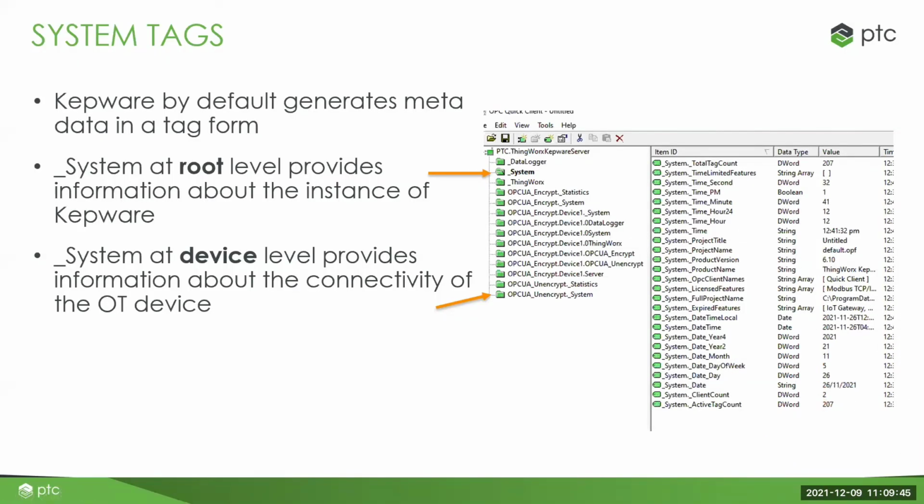For example, in certain cases maybe an HMI has some bug in it, and it starts to connect and doesn't disconnect. So the count increases abnormally, right, to 100 or 200. That's where you know that something's going on with the software itself. There's a lot of clients connecting, right? So hopefully it's just a software bug from the HMI or another client, not a real cyber attack where they're trying to do a DoS on you, right? So hopefully that's not happening.